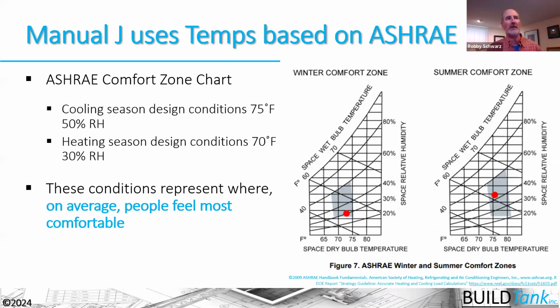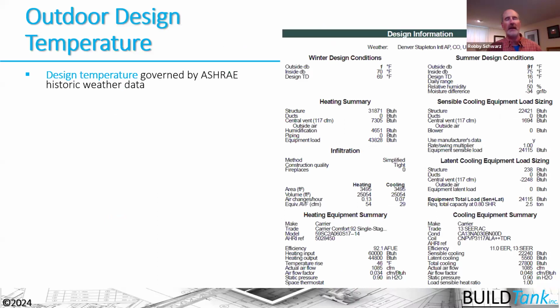So the indoor design temperatures are defined and created by ASHRAE. ASHRAE is an organization that creates a number of standards. They created this comfort zone chart, which is basically an average temperature where people feel the most comfortable. We see that in the wintertime zone, it's in that 72 range, and in the summertime zone, it's in that 75 range. And that's ultimately where the code got those temperatures. Now, the outdoor design temperatures are also governed by ASHRAE, but they're not defined specifically within the IECC as the indoor temperatures were. For these temperatures, the code jurisdiction is going to look at the specific climate location for that particular jurisdiction and determine the outdoor design temperatures.